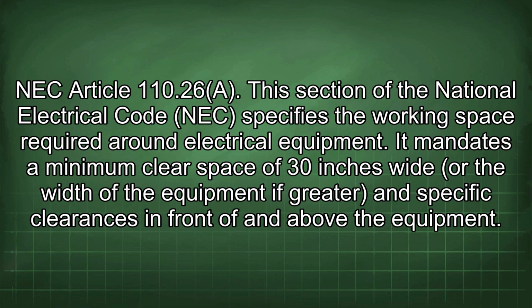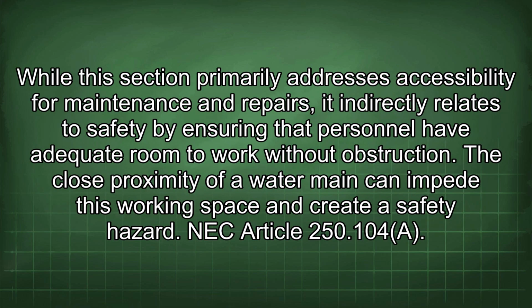It mandates a minimum clear space of 30 inches wide, or the width of the equipment if greater, and specific clearances in front of and above the equipment. While this section primarily addresses accessibility for maintenance and repairs, it indirectly relates to safety by ensuring that personnel have adequate room to work without obstruction. The close proximity of a water main can impede this working space and create a safety hazard.